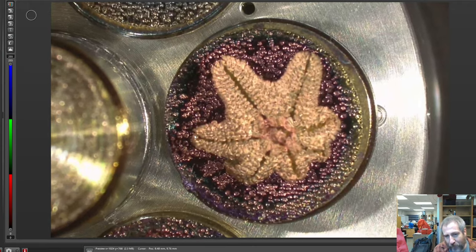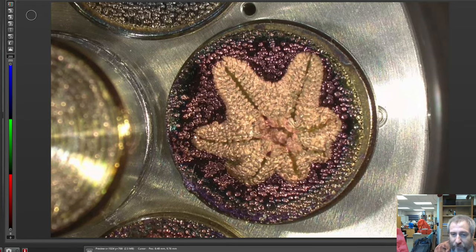Just so that you can get to see what happens when we sputter coat stuff. Everything that goes on to the scanning electron microscope that isn't conductive needs to be made conductive. The way that we typically do that is put it into the sputter coater, which deposits a very fine layer of gold on it from a plasma cloud. The little gold foil disc that's the target in there has a current run through it, and it creates a little plasma cloud, which then deposits the gold on whatever's in the chamber. So it's not a lot of gold, but if you were wondering what that looks like, when I put it into the SEM, you don't actually see any of the color. You're only seeing things in black and white. So I thought it would be kind of neat to...